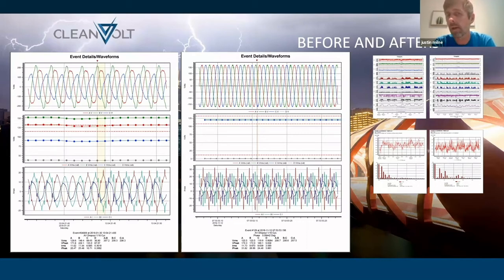Without addressing the wiring condition, the CleanVolt unit was installed on this service. And we went back later to test after time had gone by, allowing the system to naturally restore itself and some of these residual negative effects to be worked out. And as you can see, the sine wave was now much more symmetrical. Its peak to peak was more proper. And each one of the phases was laid right within its parameters at 120 volts where it should be.